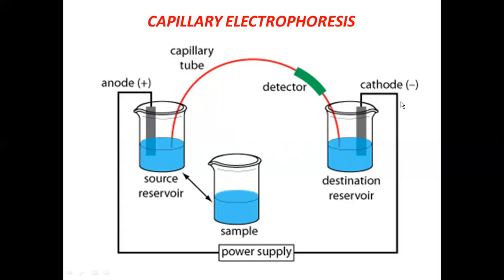The source reservoir contains the anode and the destination reservoir contains the cathode. The terminals of the anode and cathode are connected to the positive and negative terminals of the power supply device, making the anode positively charged and the cathode negatively charged. The sample is introduced into the capillary tube from the source reservoir, which has a direct connection to the sample reservoir.